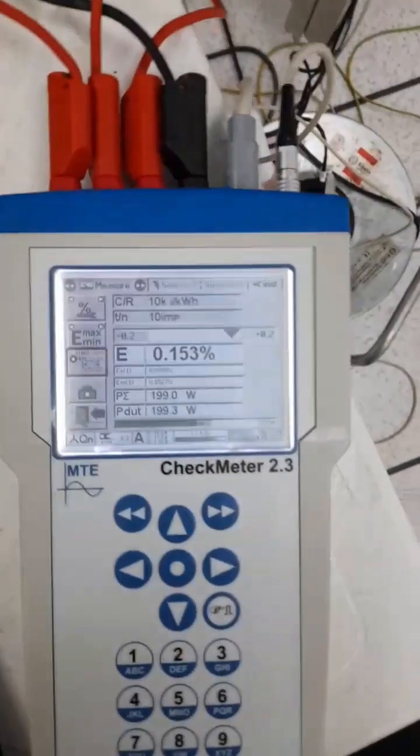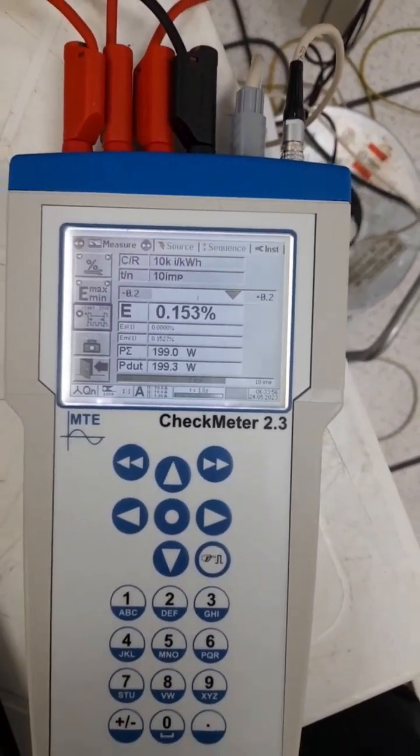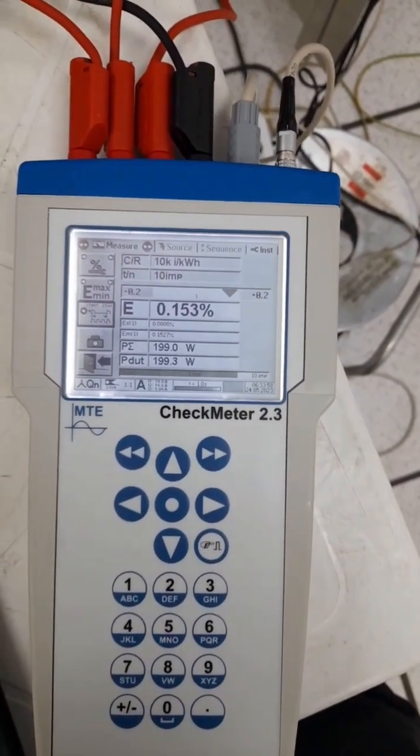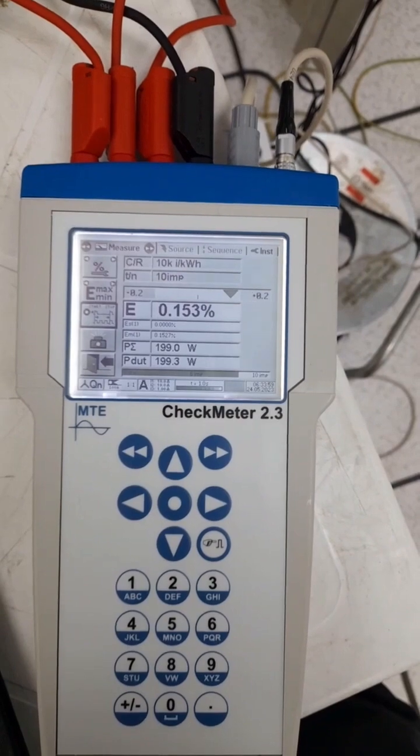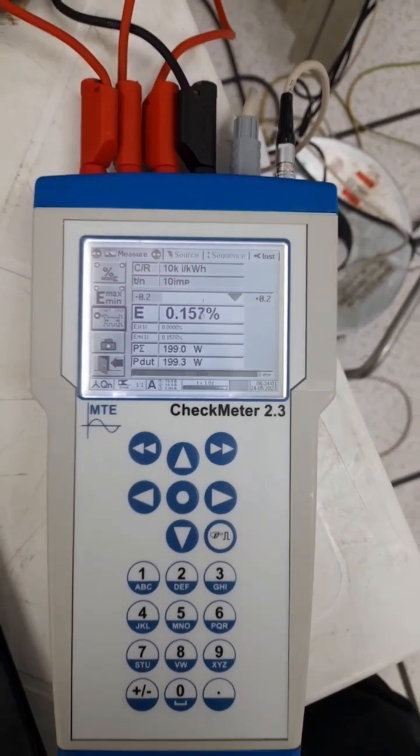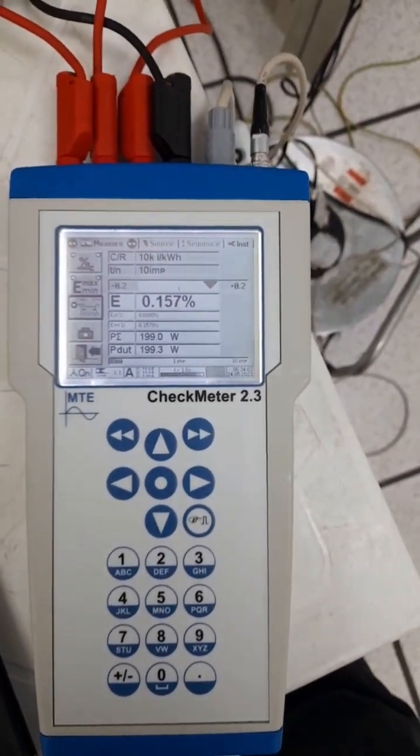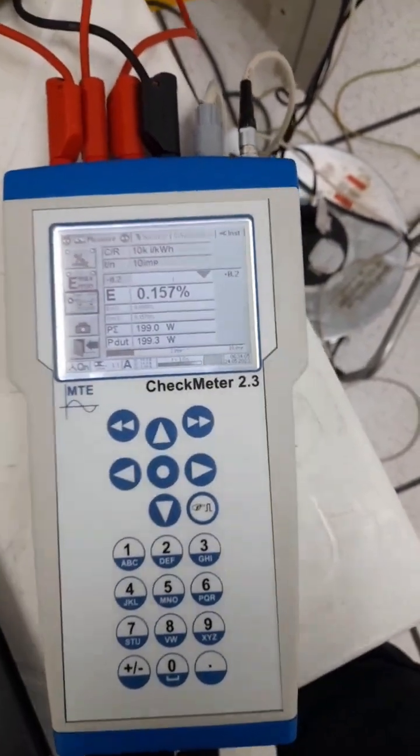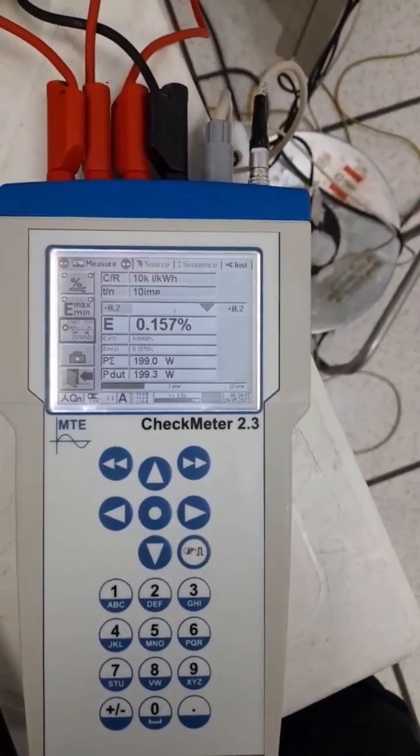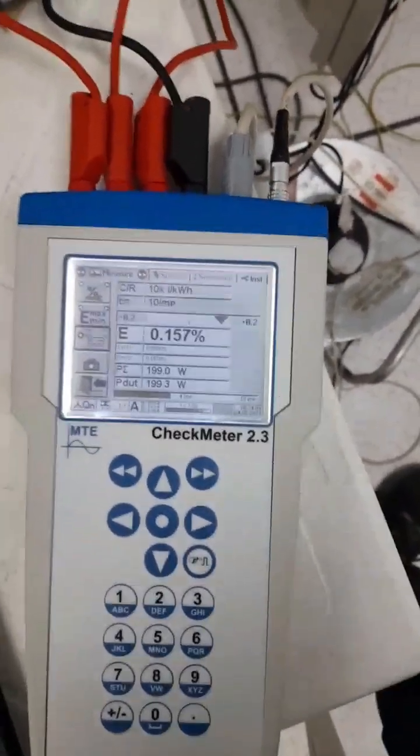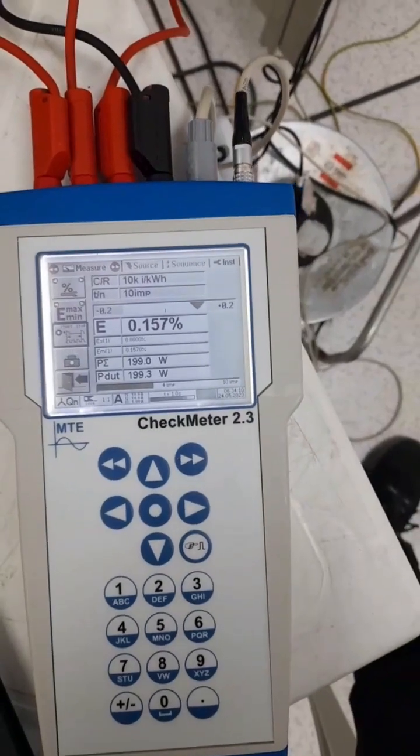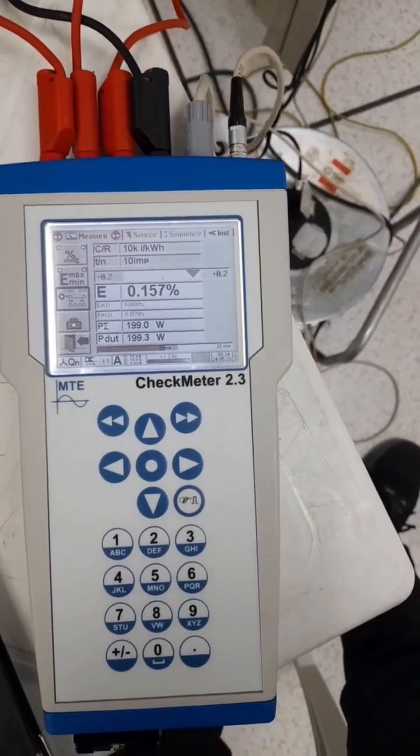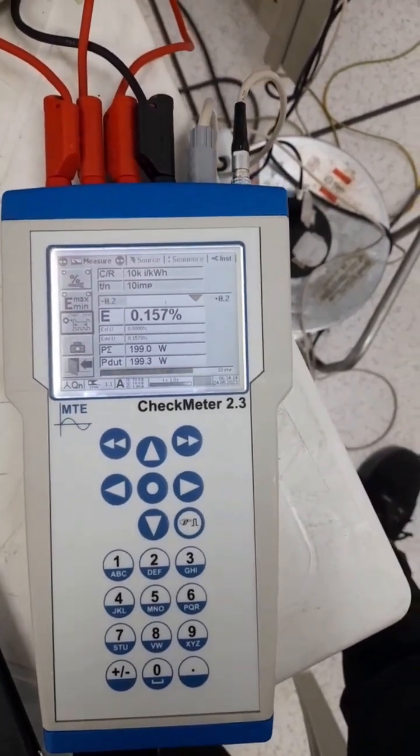I'll show you exactly what will happen. Now P summation active power is 199 watts. It was calculated based on the secondary value that we are injecting. Now I'll show you what will happen if the clamp is not fixed properly or if it is in the opposite direction. Your error will be high.